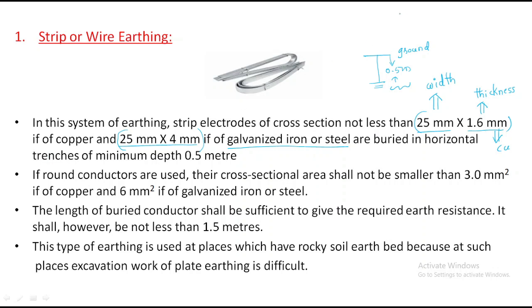Understand? But look at here. Here for the copper we are using 25 mm by 1.6 mm, but here for galvanized iron 25 mm by 4 mm. The thickness is more because, compared with galvanized iron or steel, copper has more conducting properties. That's why we are using less material. Understand? But for both, the depth must be 0.5 meter.